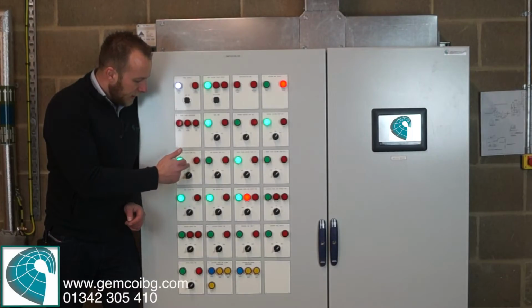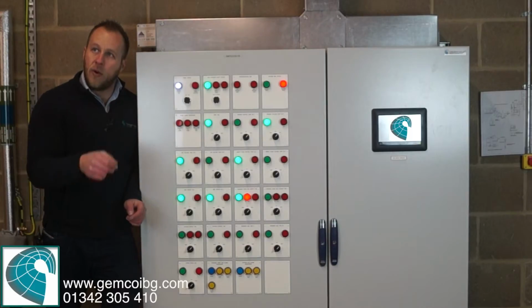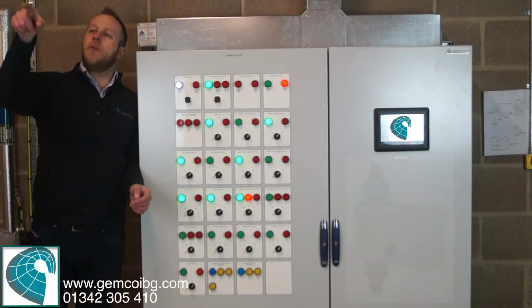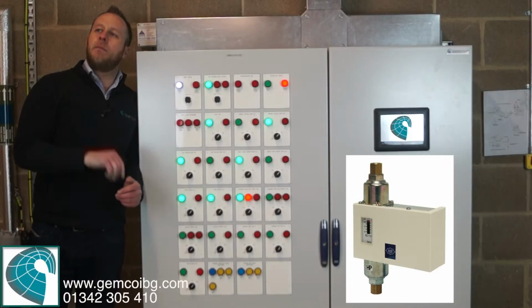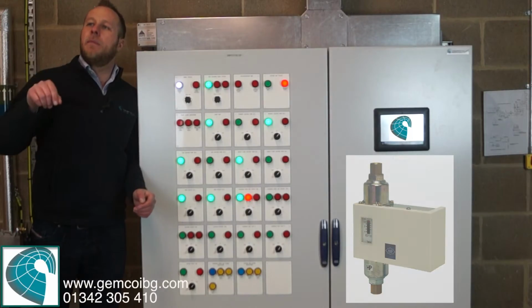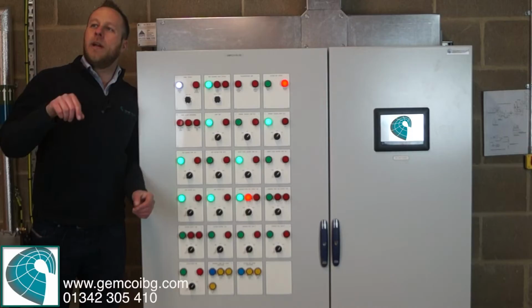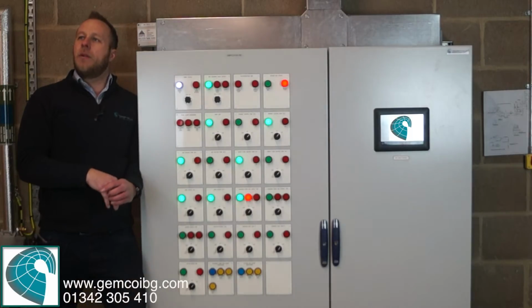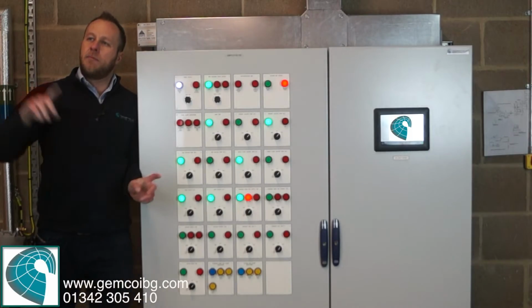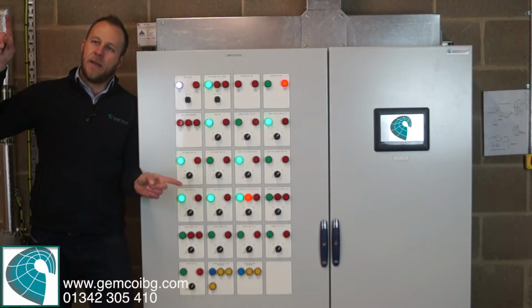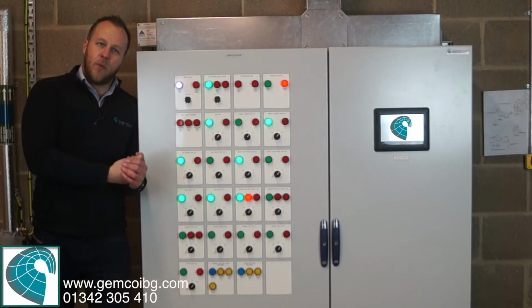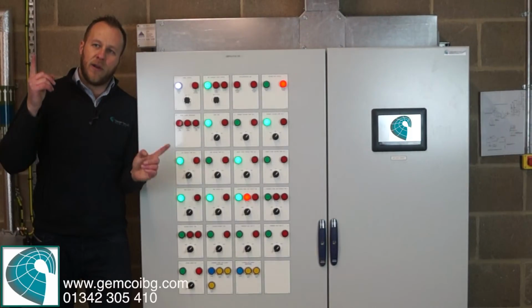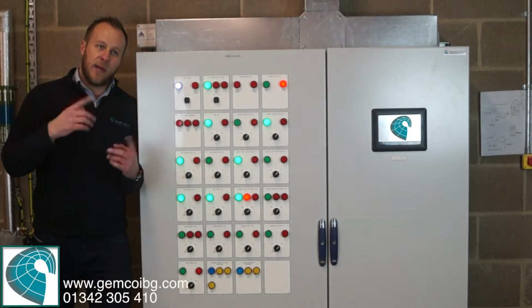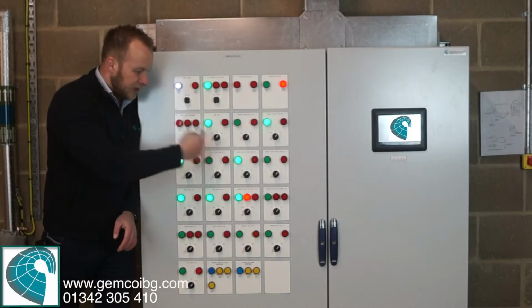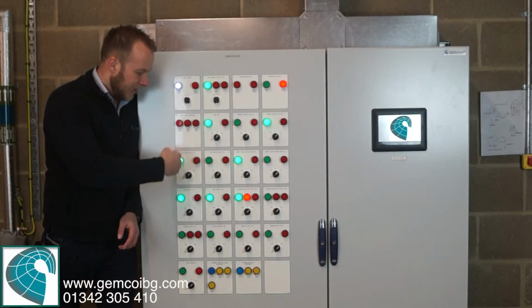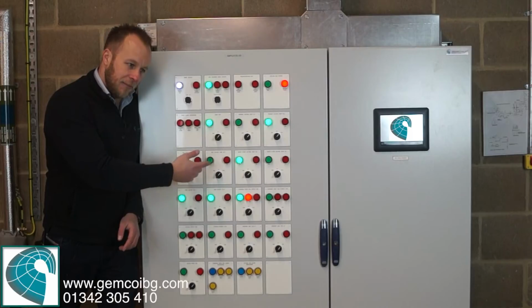When the duty pump is enabled, we monitor flow across that pump for 60 seconds. You'll see little white devices with copper pipes going either side of the pump. They're mounted on the wall there, and you can see the tiny little copper pipes either side of the pump. That just monitors the differential pressure across the pump set. So we say, start duty pump 1, have we got flow, have we got flow, have we got flow for 60 seconds. If we haven't got flow, we shut that pump off and we start pump 2, and we start that process again.